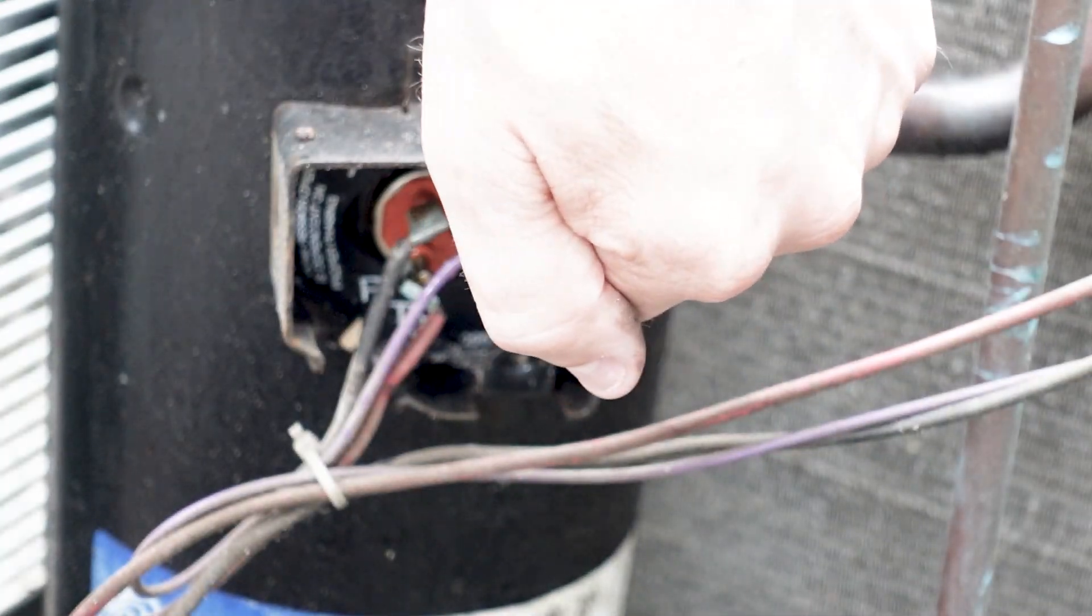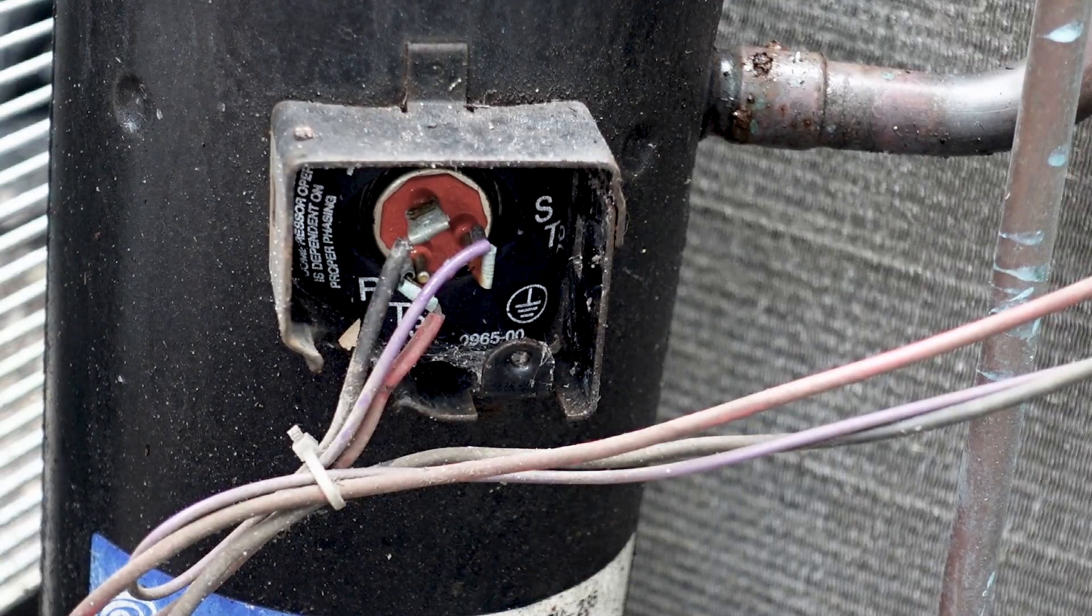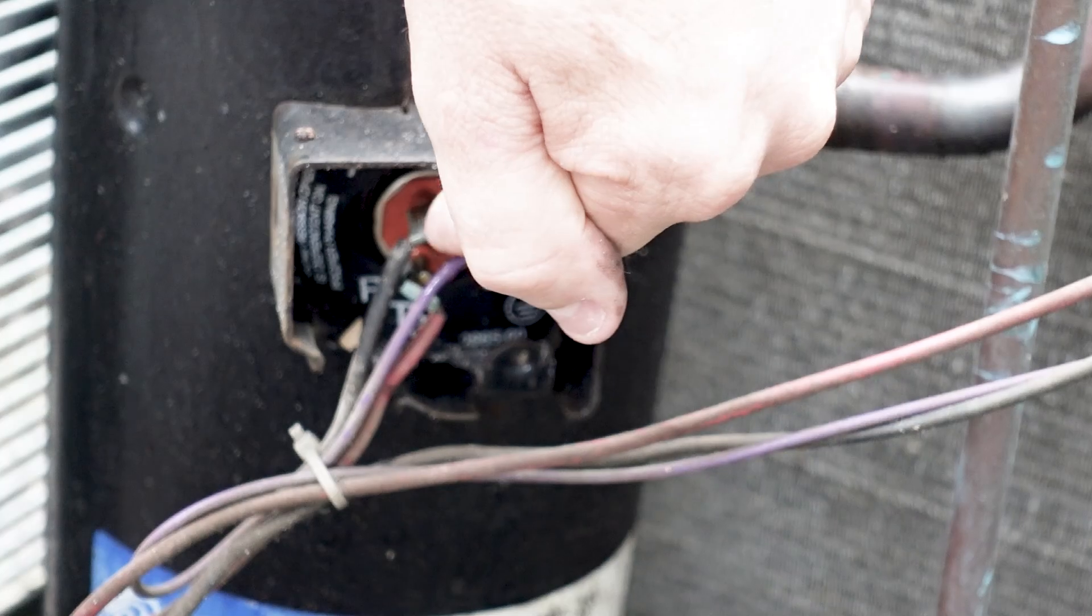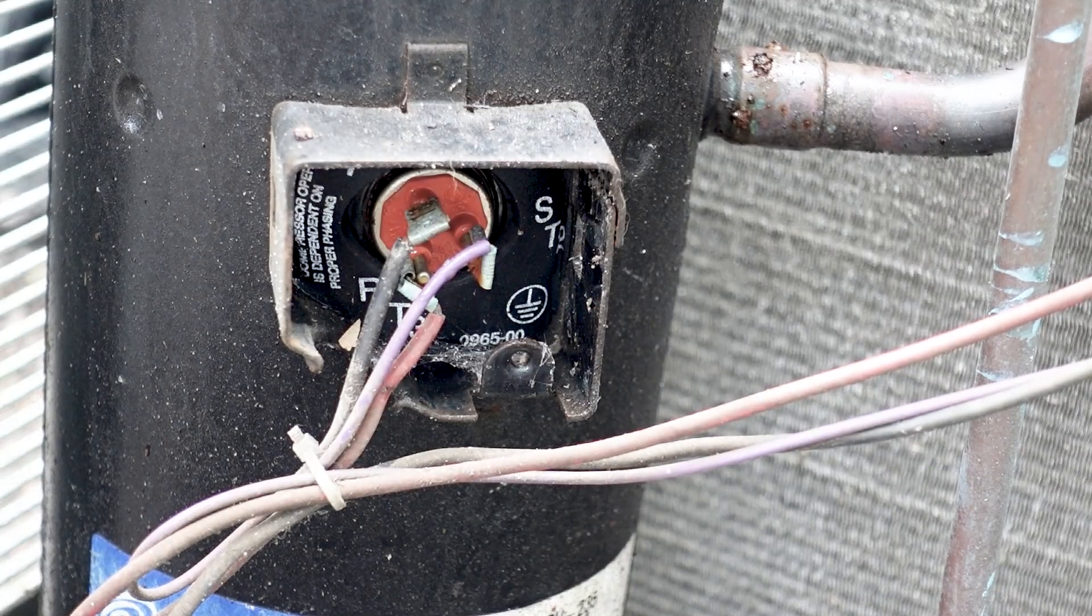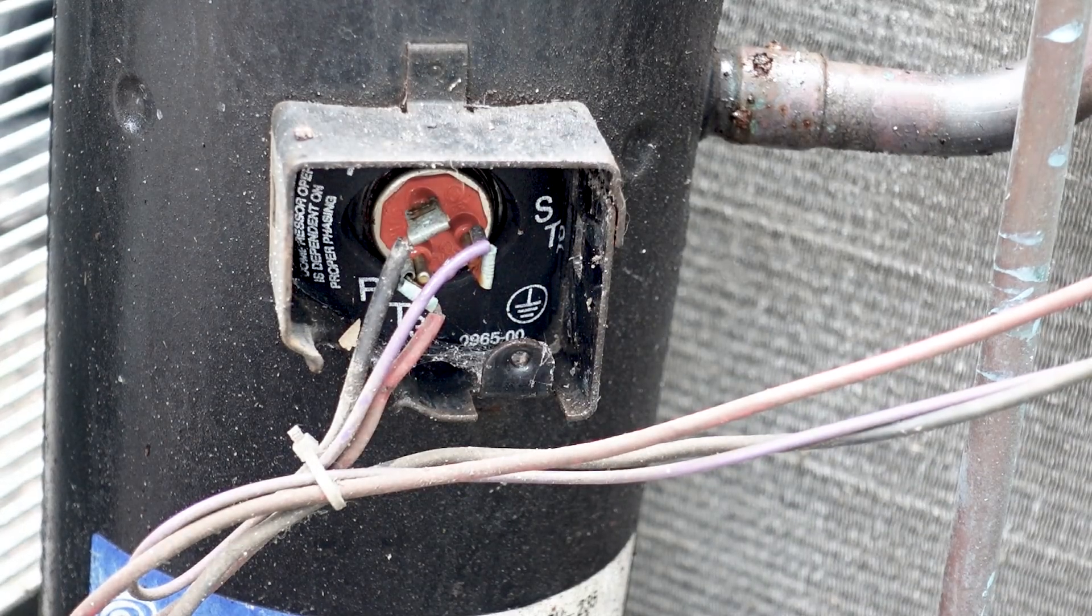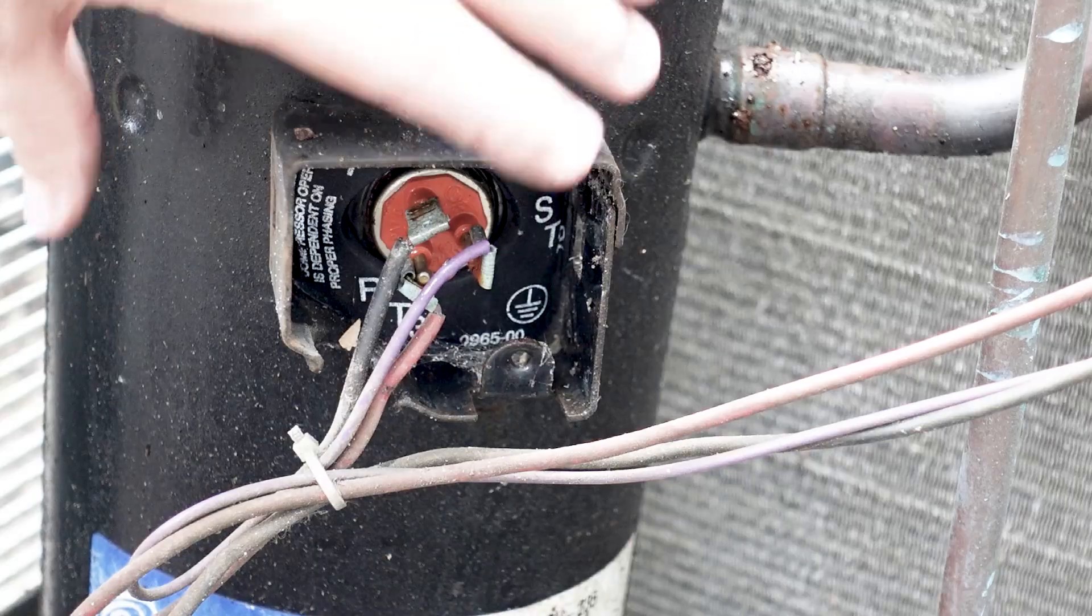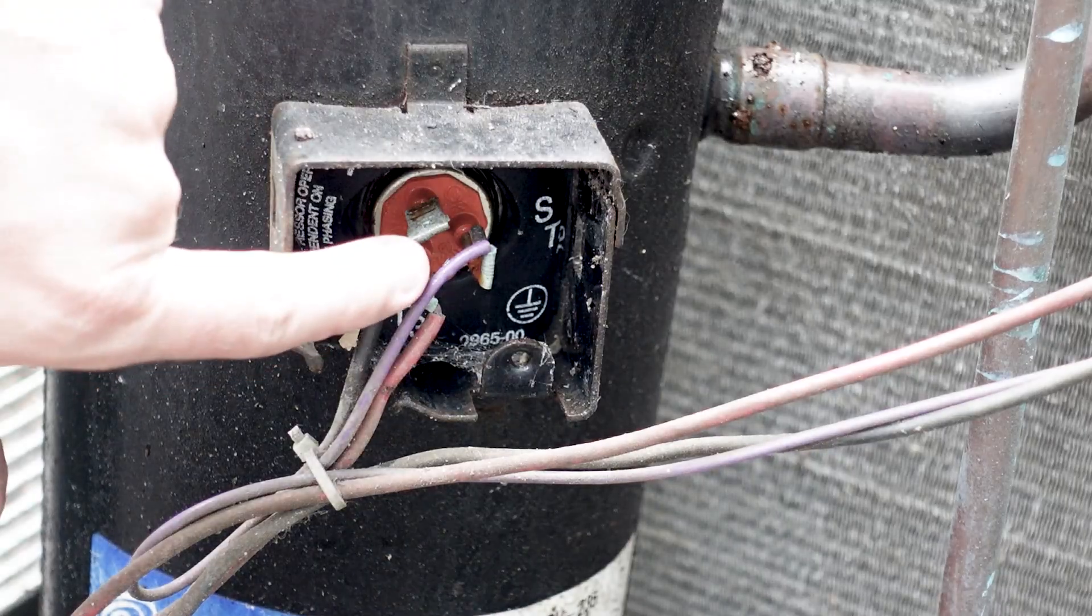So inside this compressor, there are two windings that connect to this common point. And also directly behind this terminal is where our internal overload is. So if our motor overheats in our compressor, it's going to open up to shut it off to protect it.